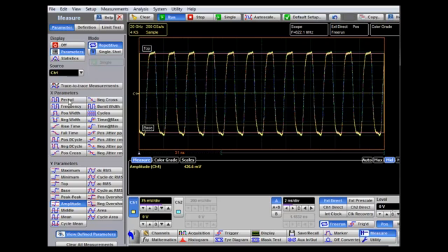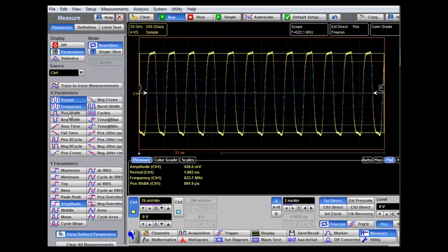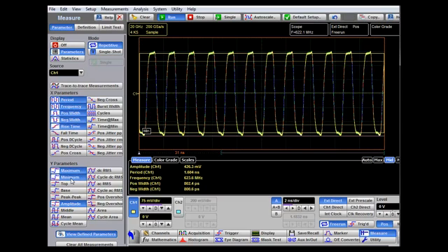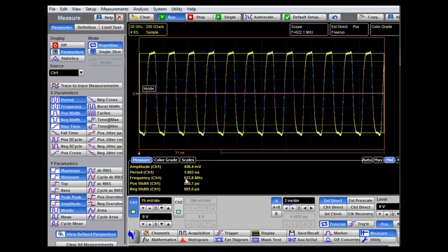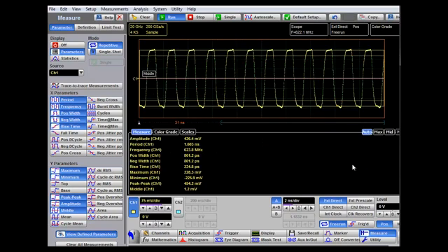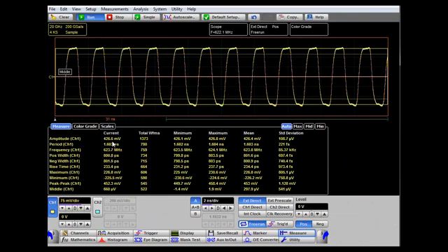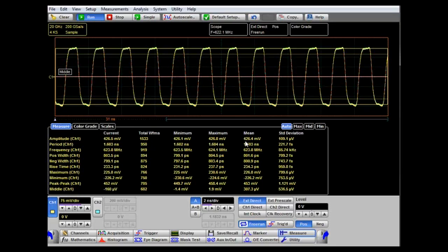We can turn on up to 10 measurements at once — for example, 5 time measurements and 5 amplitude measurements. Selecting auto will automatically scale the measurements box to display all 10 measurements being updated in real time. More information can be displayed using the statistics view, where we can see the total number of waveforms acquired, the minimum, maximum, mean value, and standard deviation of each particular measurement.